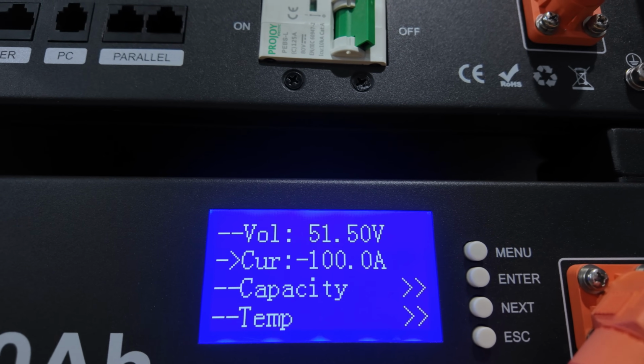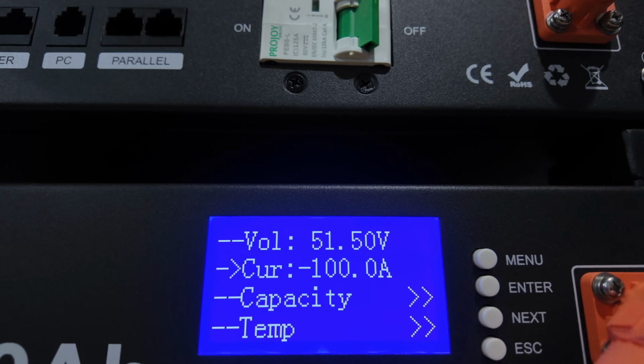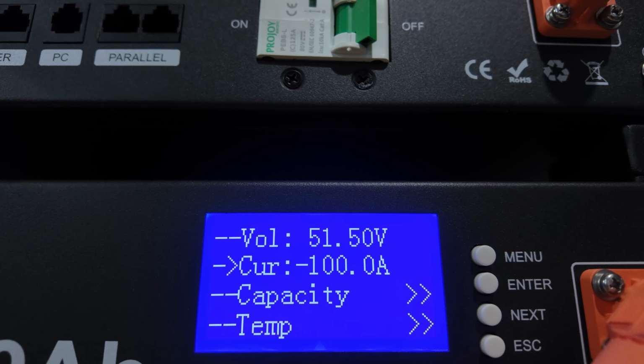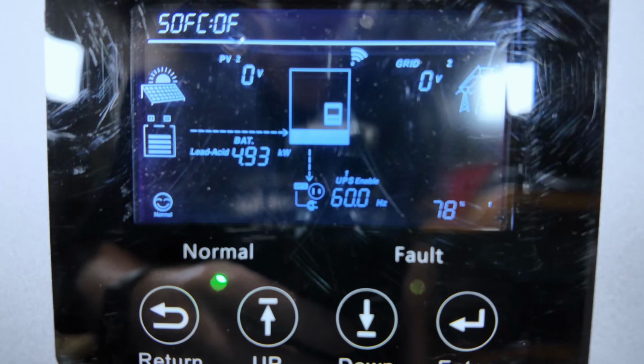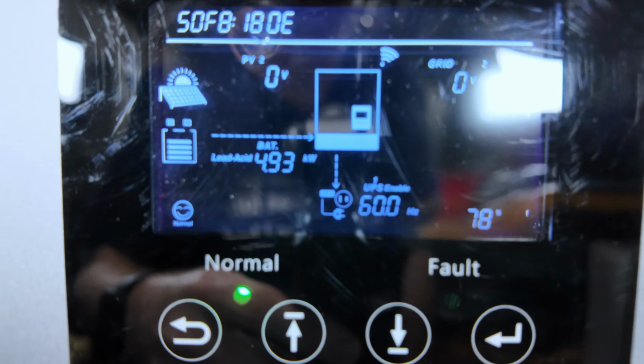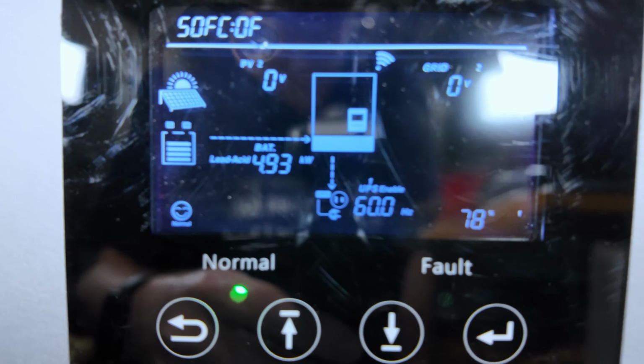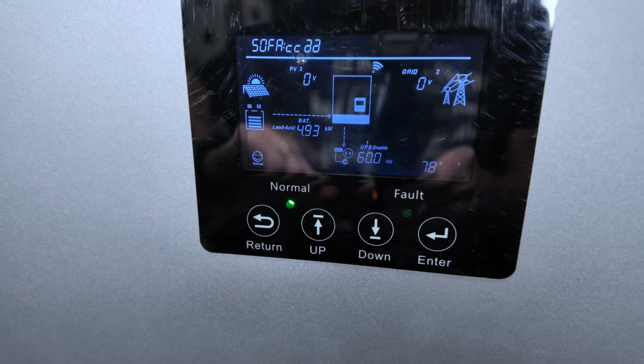So we're discharging from the battery at 100 amps on my nose. Obviously, as the voltage changes, that current will change as well. And from the inverter standpoint, 4.93 kilowatts going into the main battery bank. Current time is 5:27. So while the discharge test is running, I want to show you how this battery can communicate with different styles of inverters. So we'll look at connecting it to the EG4 6000 XP. We'll look at connecting it to the MidNite inverters. And then we'll also look at connecting it to the Victron inverters.